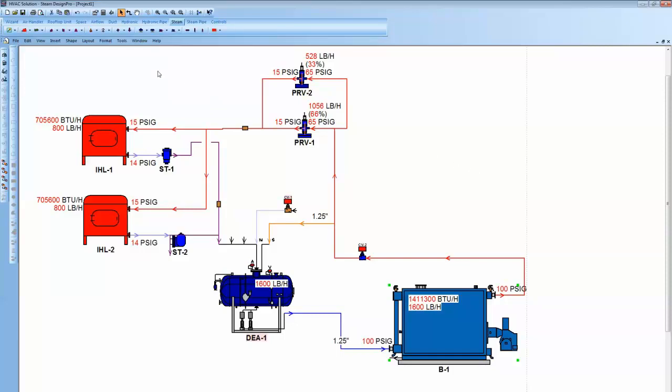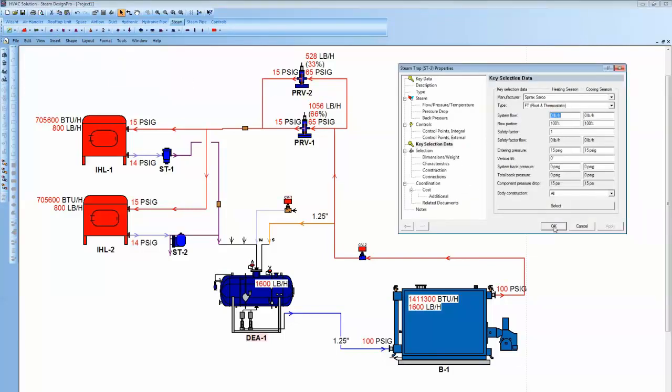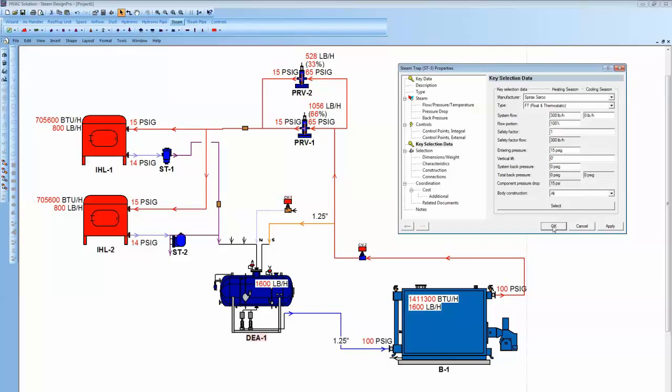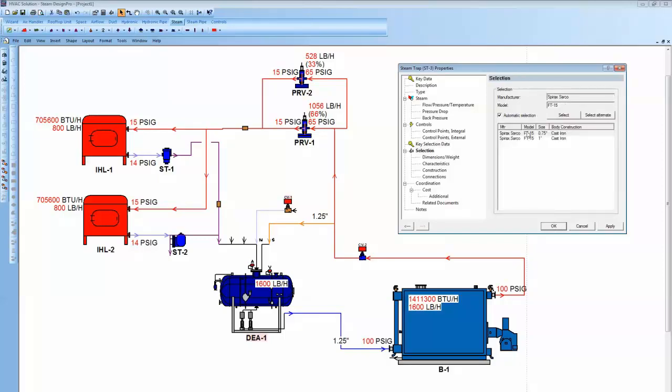Now, you don't have to necessarily have your product in a system to do selection. In other words, I could just go grab a trap up here and drop it on the screen and click on that trap. And what I do, it takes me to this key selection data. That means I just have to type in a load of 300 pounds per hour. It has a safety factor defaulted to 1. Pressures defaulted to 15. And then I can just hit okay and choose to select here and it'll select the trap.